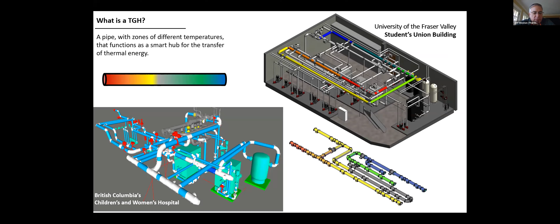The heart of the system is a chiller, which is also the building's primary heater. In fact, if we were to call it a heater, it would be more accurate, because the amount of heat produced from a chiller is more than the amount of heat it collects as being a cooler. So what makes the chiller efficient is lowering the heating temperatures and raising the cooling temperatures. And that's what the TGH really does.